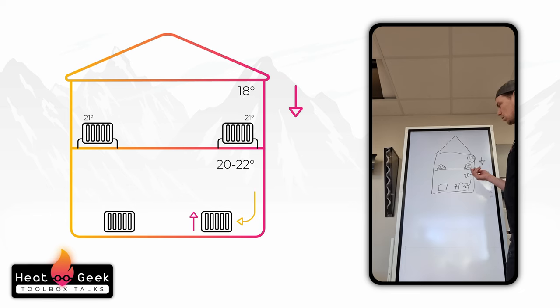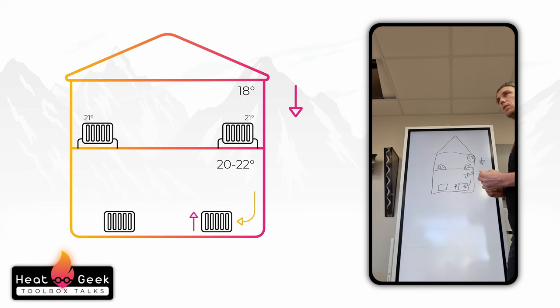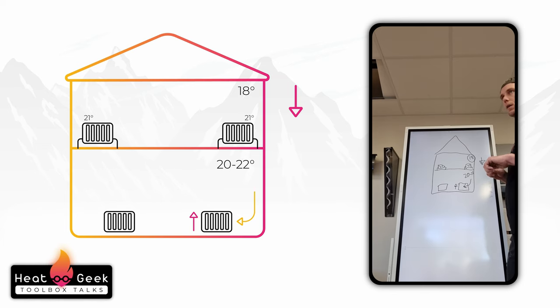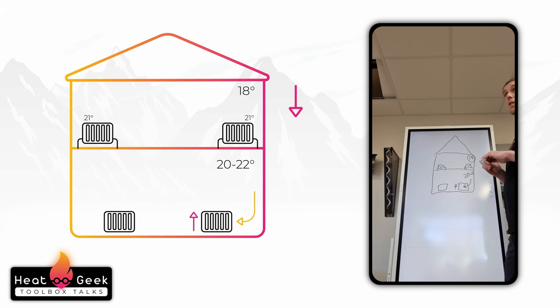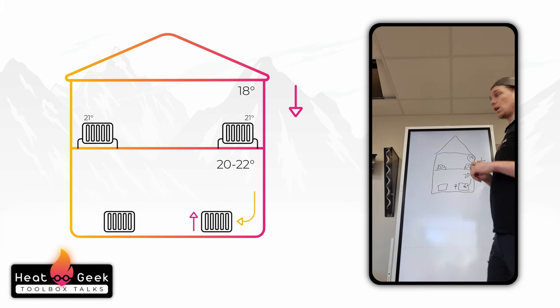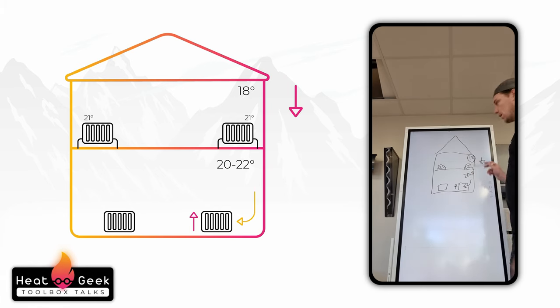You could do it with balancing or you can do it with two TRVs. When it gets back to the plant room they just assume that they have to put a zone valve on it, but really they just need to go into a 28 mil pipe and distribute. They could just put a globe valve on it and just balance it.